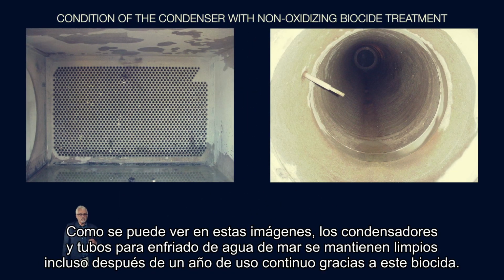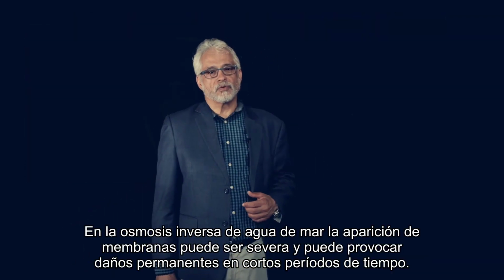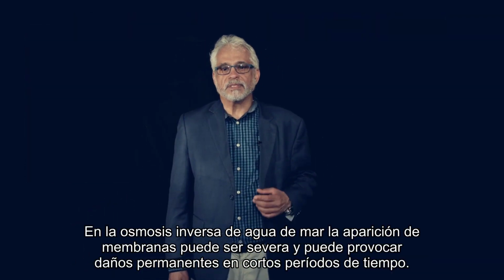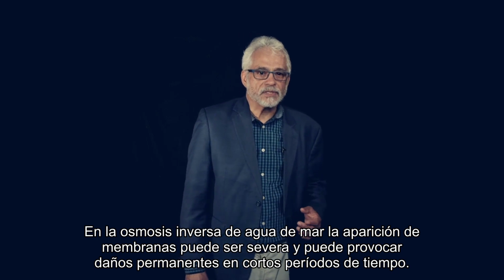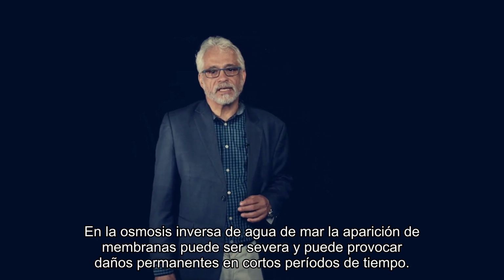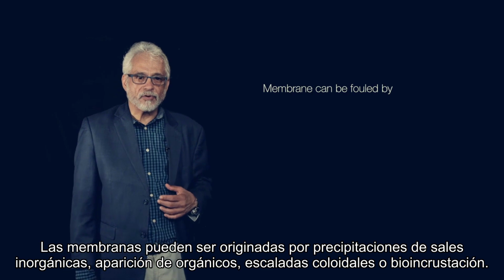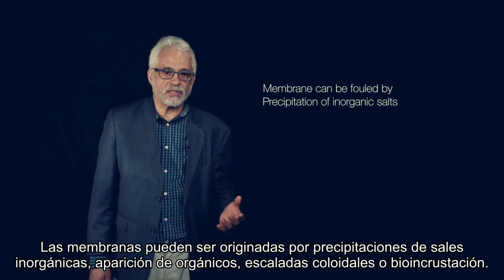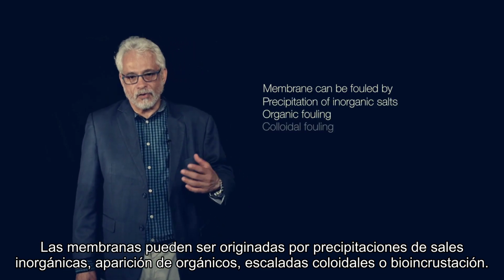As indicated in these pictures, condensers and seawater cooling pipes stayed very clean after more than a year in continuous operation with this biocide. In seawater reverse osmosis, fouling of membranes can be severe and lead to permanent damage in a very short period of time. Membranes can be fouled by precipitation of inorganic salts, organic fouling, colloidal fouling, and biofouling.